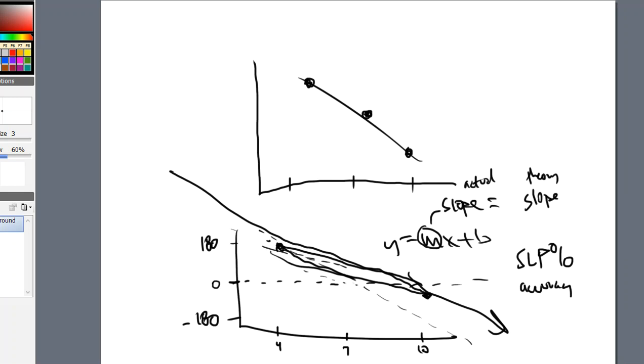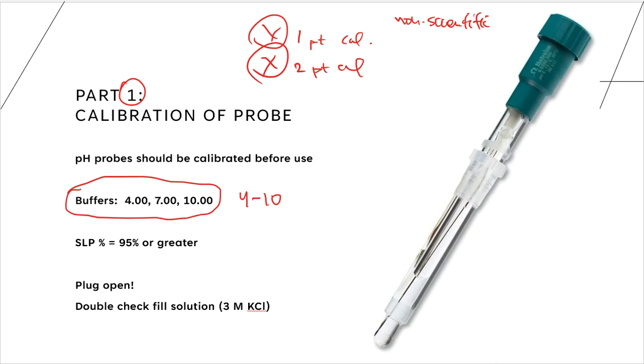So 3 is better than 2, and 2 is better than 1. What we are after most of the time is something greater than 95%. So when I complete the calibration curve, this probe will send a signal to the meter. The meter will calculate the slope percent, and that slope percent will be displayed on the computer screen, and it will be a value that I can take away from the calibration curve.